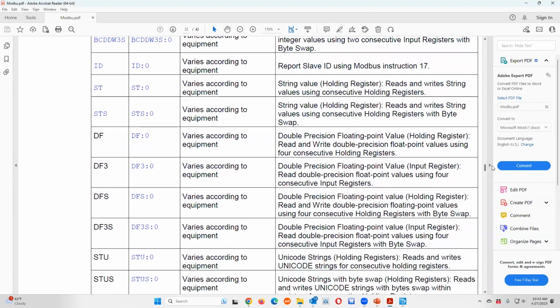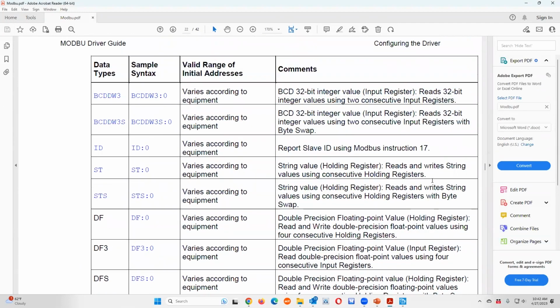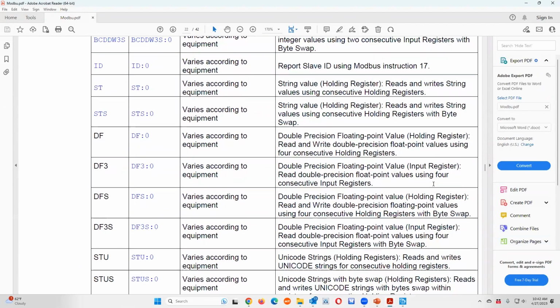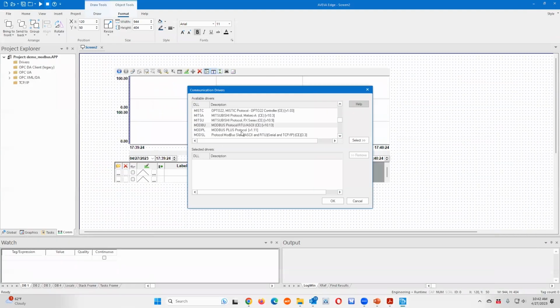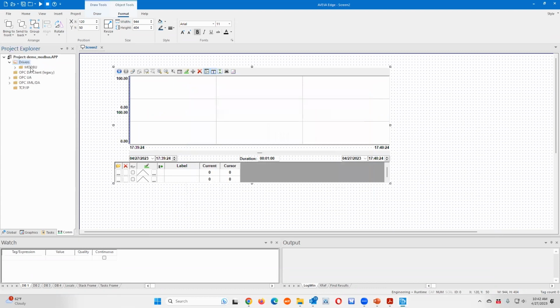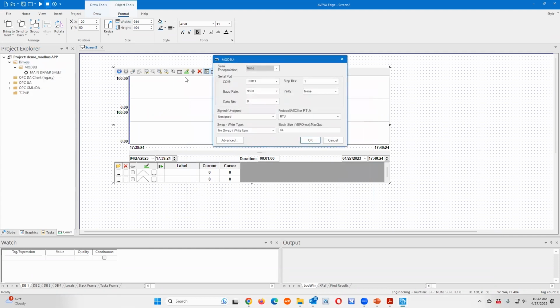For instance, if you have different types of analog values, this shows you how to format the tag value. Let's see, I'm going to close out of this. I want to be sure to speed this up so I can answer some questions as well. So we'll just do a quick example. I'll show you how to add a few tags. So I set up the Modbus driver, or selected it rather. Click OK. And you come over here, go to the main. Actually, first of all, with Modbus RTU, you need to set up the COM settings. So you would right click on Modbus, set the COM. For instance, I had this one on COM 4, I believe. 9600 8N1, that looks good.